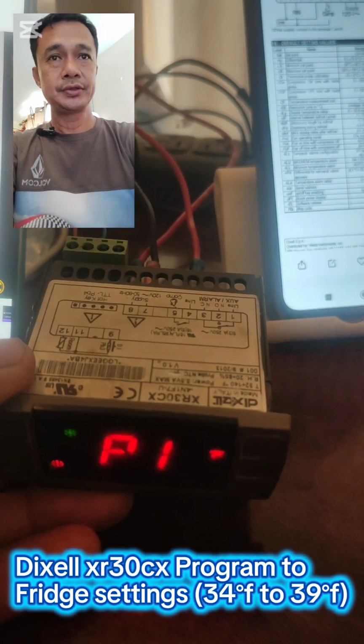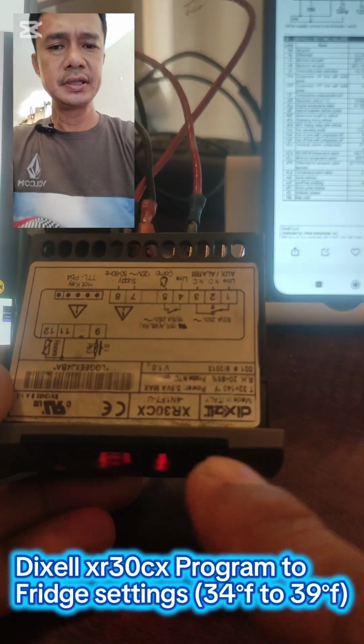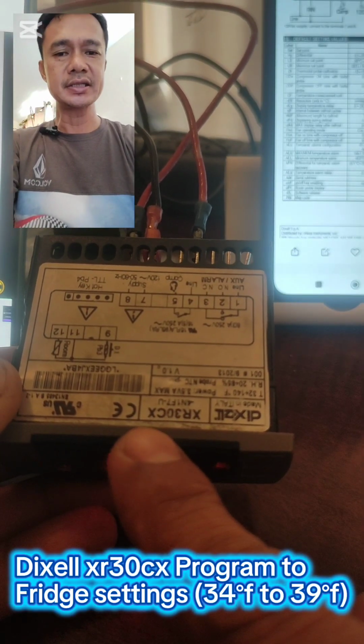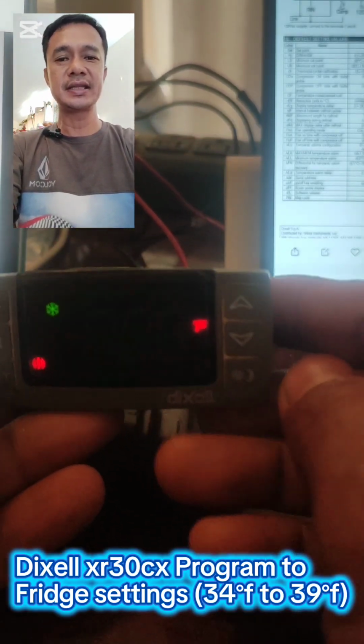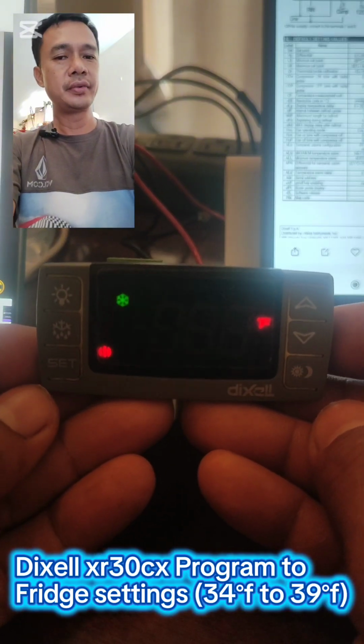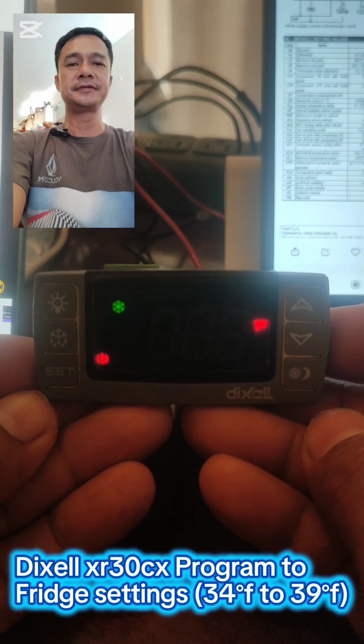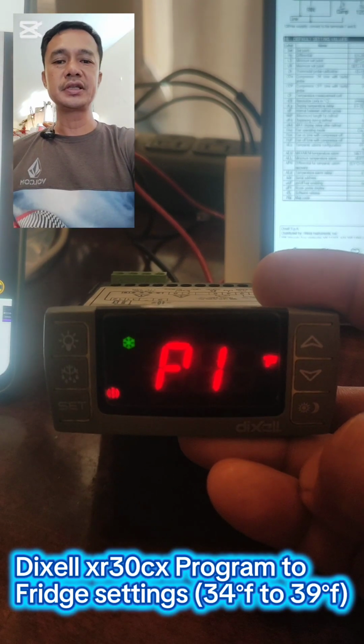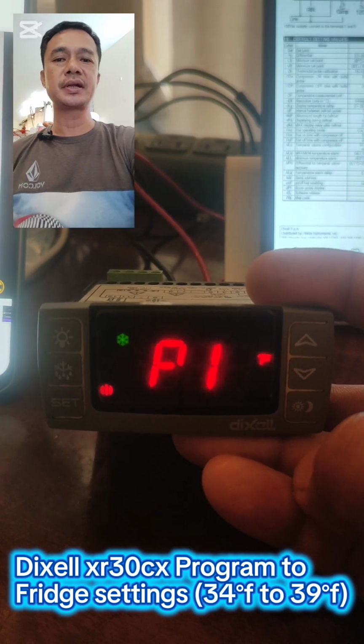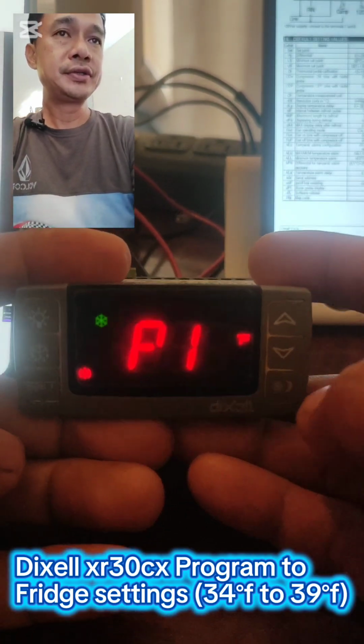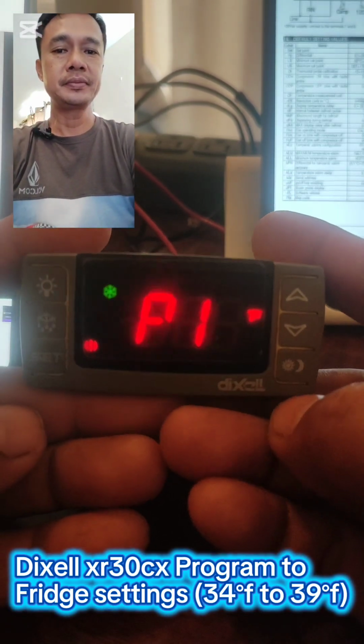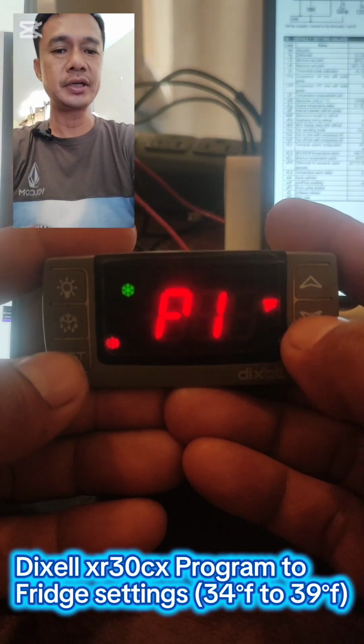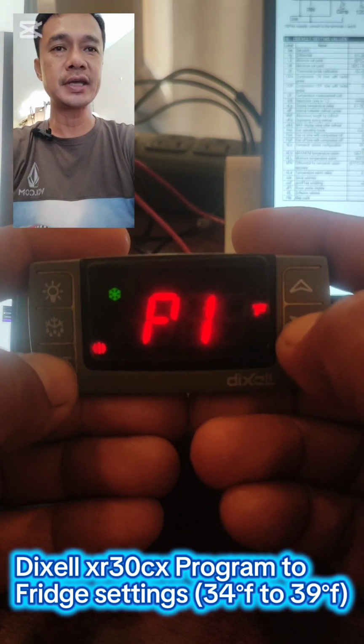Today we're going to program this Dixell XR30CX into fridge setting, or we call it chiller setting. It's 34 degrees Fahrenheit to 39 degrees Fahrenheit. We're going to enter the programming by pressing the set button and the down button for 3 seconds.